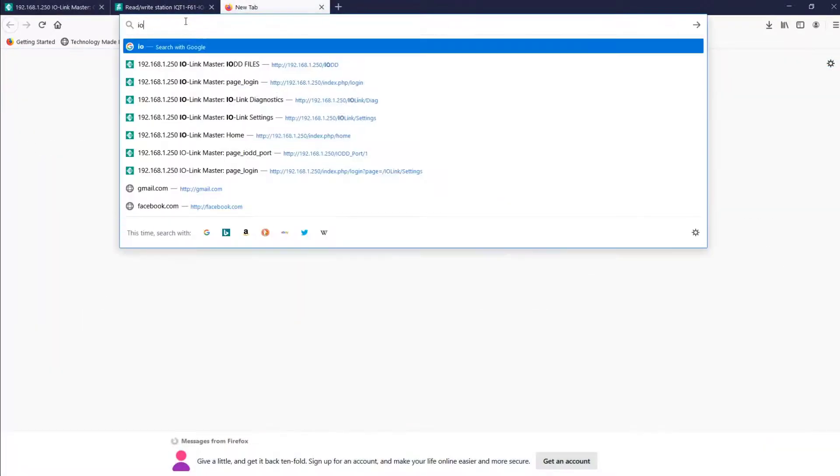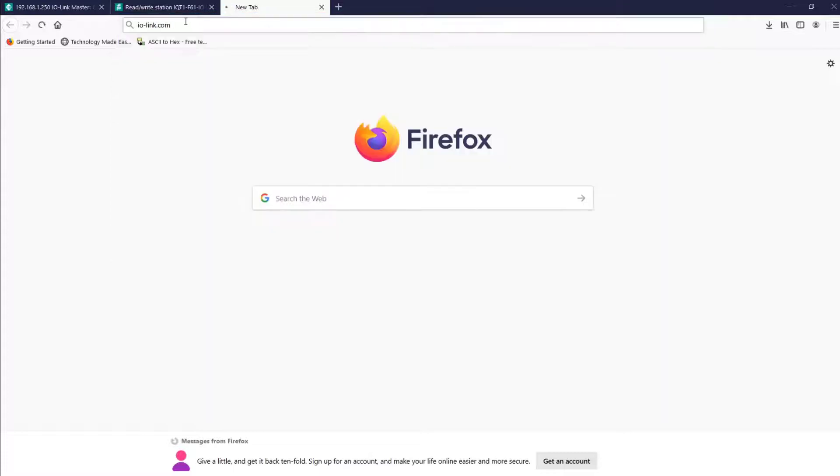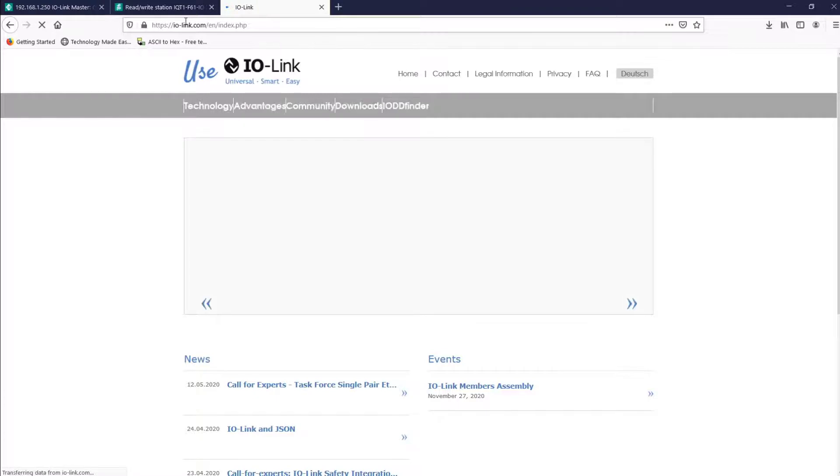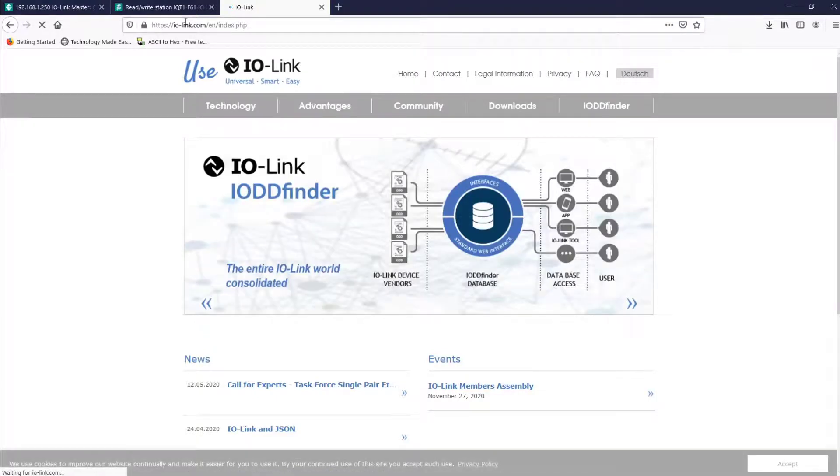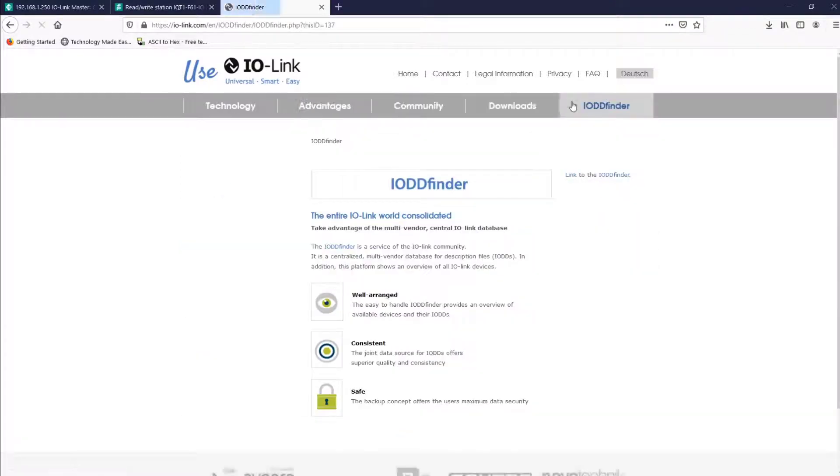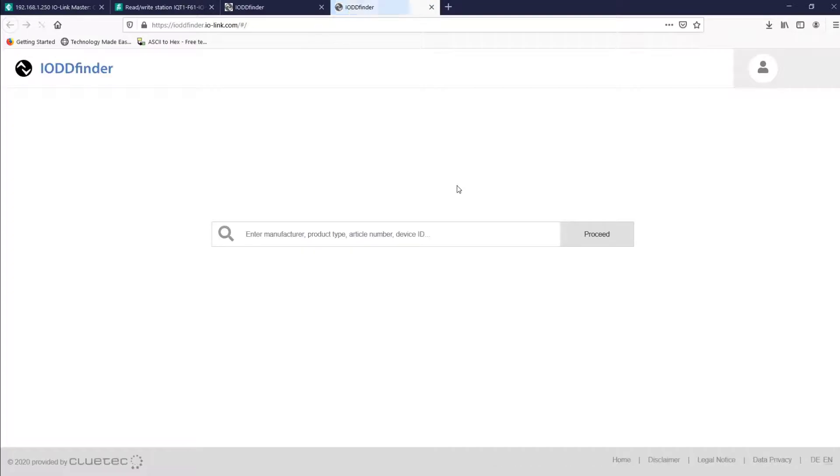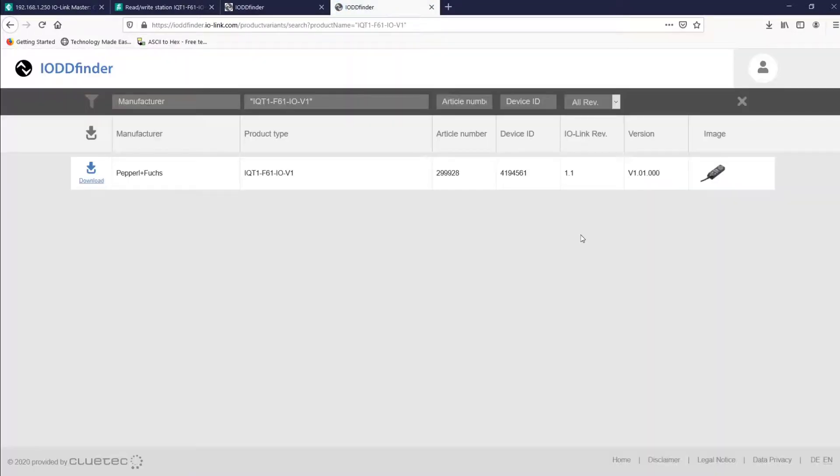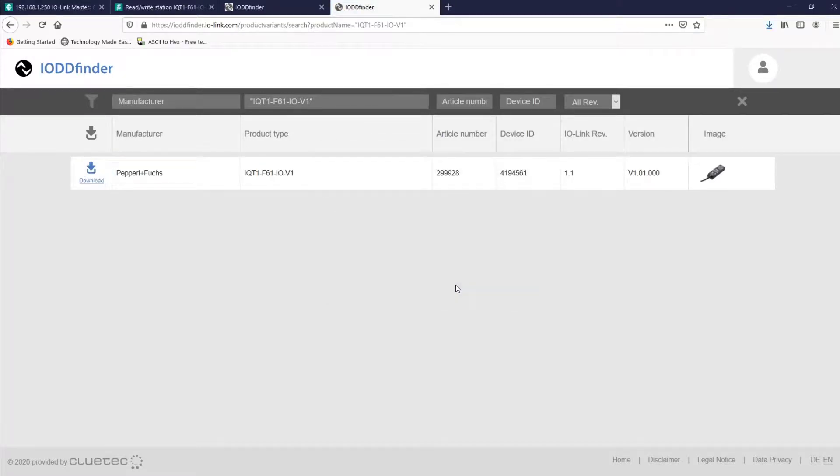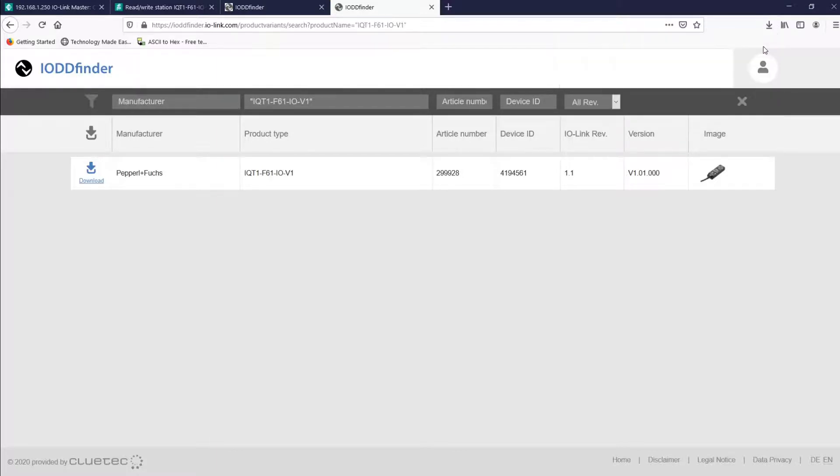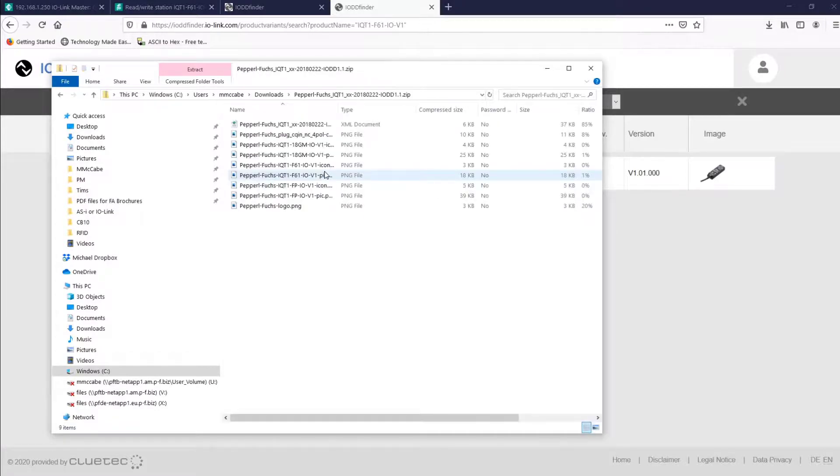And the second option that we have to locate an IO-DD file is iolink.com. So once you type in that address, we're going to find the IO-DD finder, and then we'll wait for that to load. So go ahead, type in the model number. Download, and notice that it gives you a nicely packaged zip file, version 1.1 here of course, remove the unnecessary files, and simply upload it again to the web interface, and you'll be ready to go.